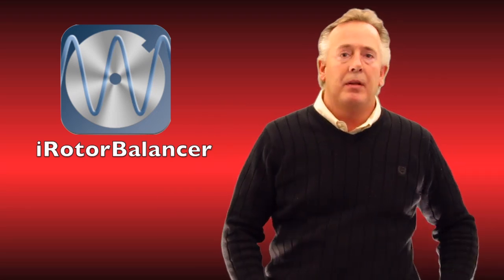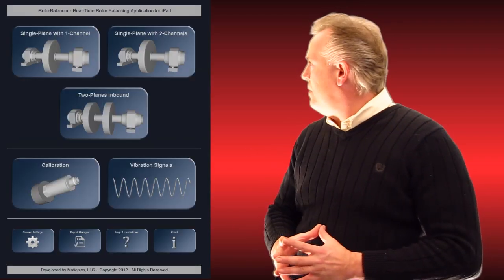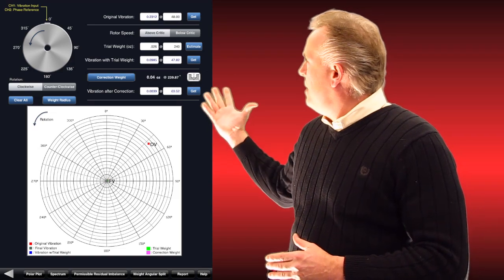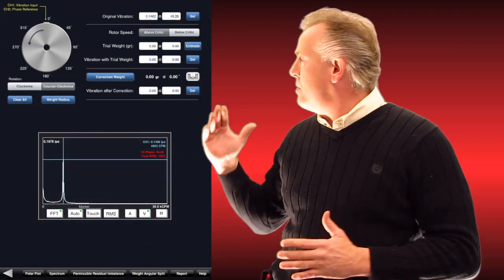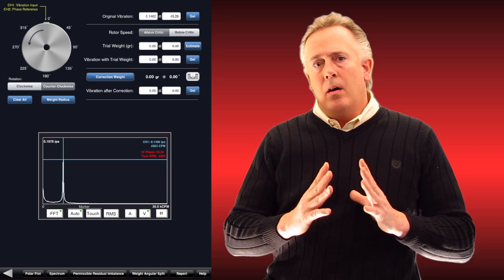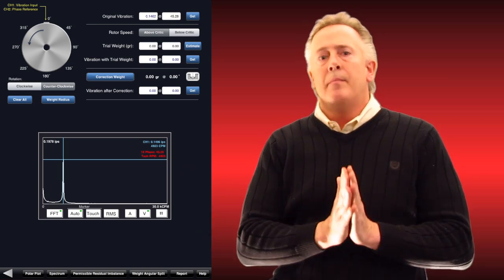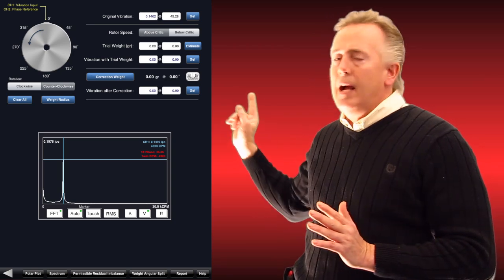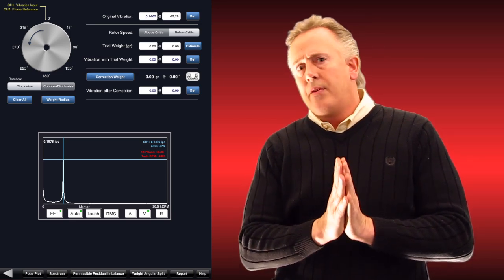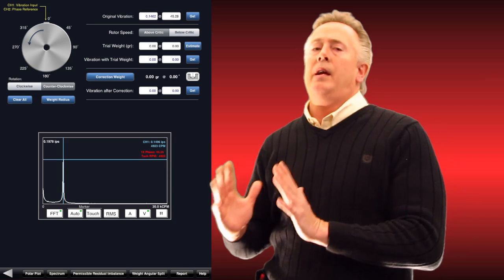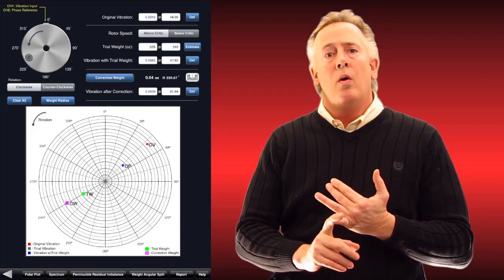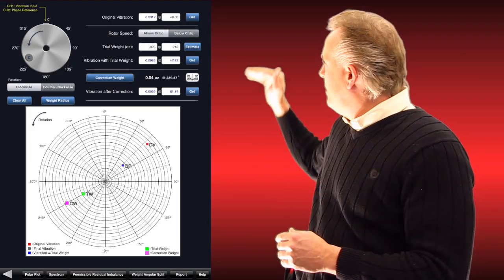I also want to show you our application on balancing. This is what the front page of the balancing app looks like. When we open the app, we can look at both the polar plot and the spectrum at any given time while we're balancing. This achieves two things: one, if we have multiple frequencies interfering with what we're trying to balance at the one times running speed, we can dial in with our spectrum right into the running speed and make sure that's all we're looking at. If we're balancing a 3600 RPM motor or pump, we're only looking at 3600 RPM. Then we can simply click a button, swap back to the polar plot, and immediately know where our heavy spot is.